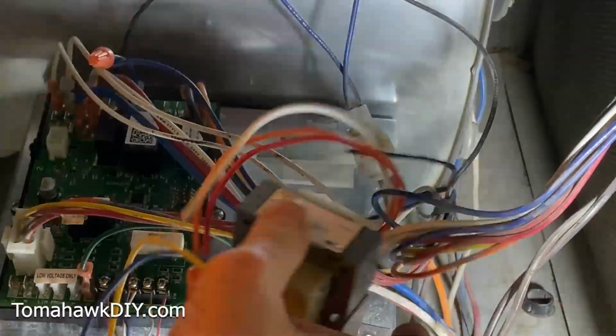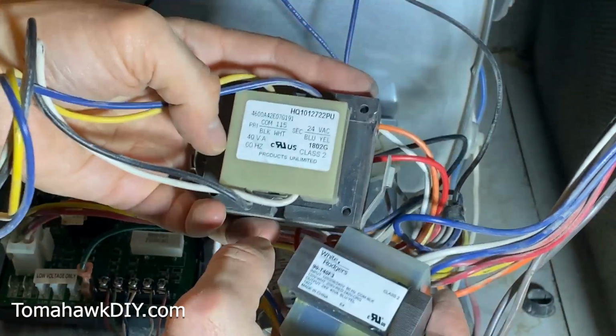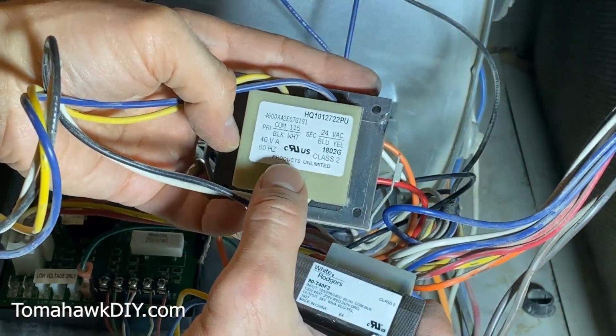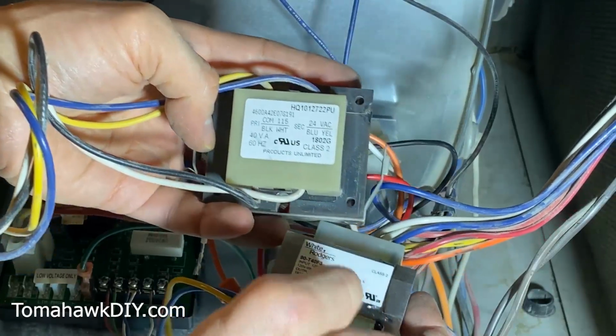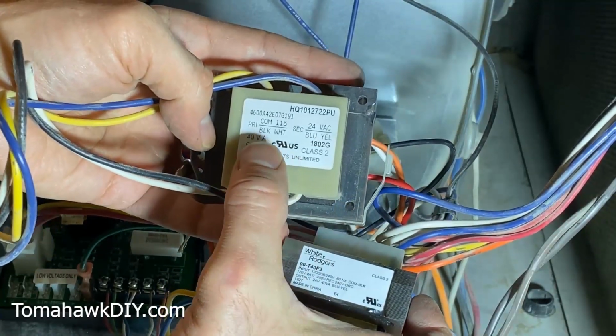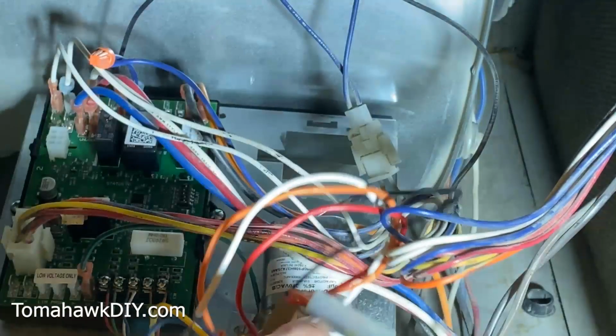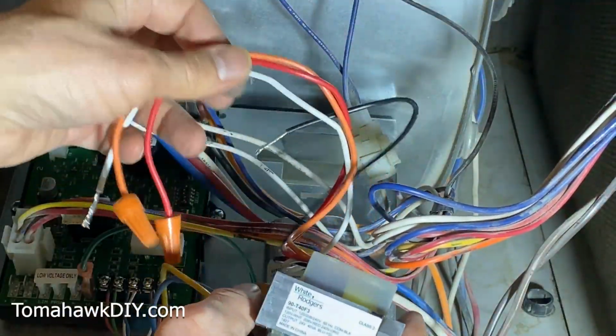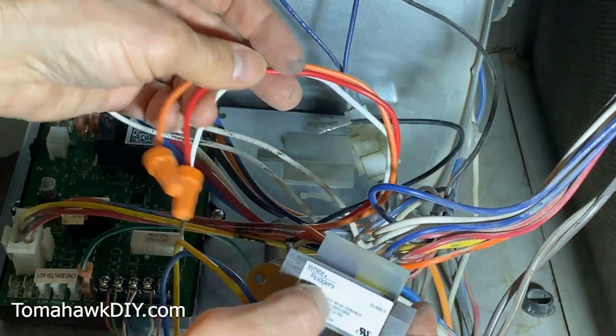So remember our transformer, we checked to make sure it's got all the same ratings: output of 24 volts on the new one as well as the old one, input of 120, etc. So this new one can take 120, 208, or 240 volts.